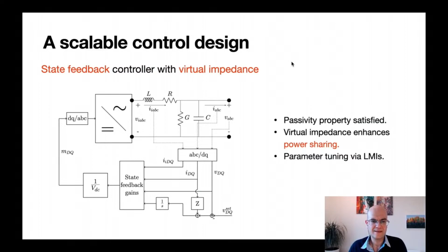In the last couple of years, we have been trying to come up with a control design for grid-forming inverters so as to satisfy this decentralized stability condition, which would give stability guarantees for our network and also allow a plug and play capability. It turns out that this can be satisfied by means of a state feedback controller used together with a virtual impedance. This virtual impedance also improves the power sharing properties of the network, particularly at faster timescales.